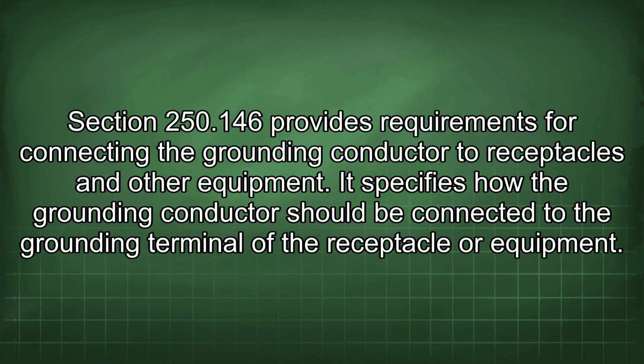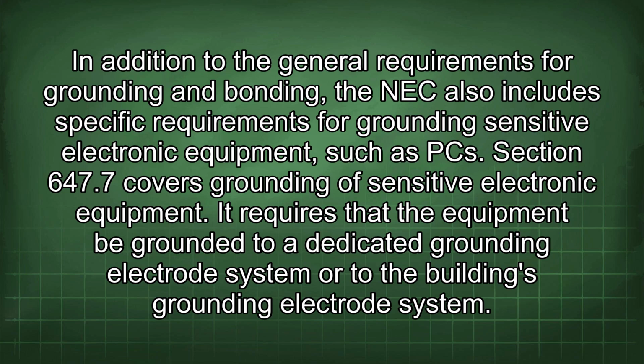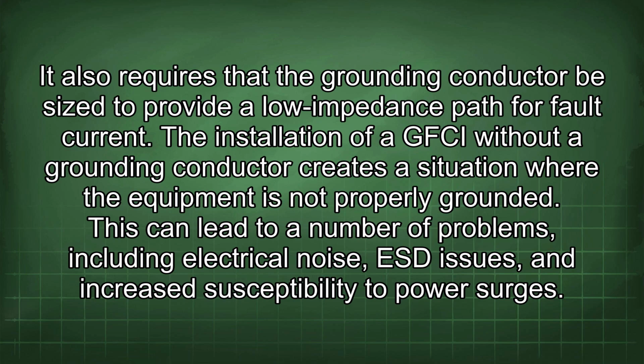Section 250.146 provides requirements for connecting the grounding conductor to receptacles and other equipment. It specifies how the grounding conductor should be connected to the grounding terminal of the receptacle or equipment. In addition to the general requirements for grounding and bonding, the NEC also includes specific requirements for grounding sensitive electronic equipment, such as PC. Section 647.7 covers grounding of sensitive electronic equipment. It requires that the equipment be grounded to a dedicated grounding electrode system or to the building's grounding electrode system. It also requires that the grounding conductor be sized to provide a low impedance path for fault current.